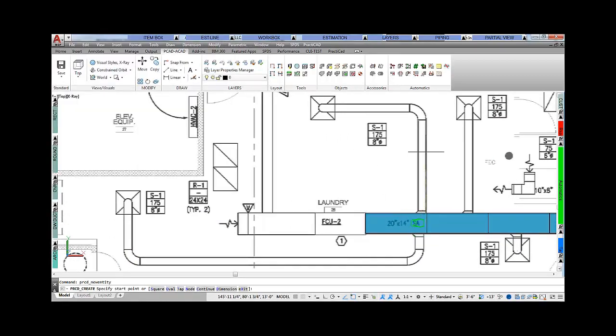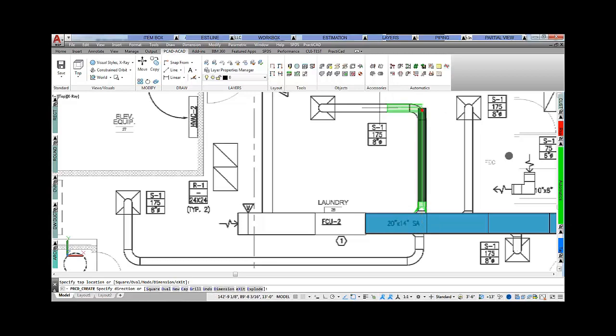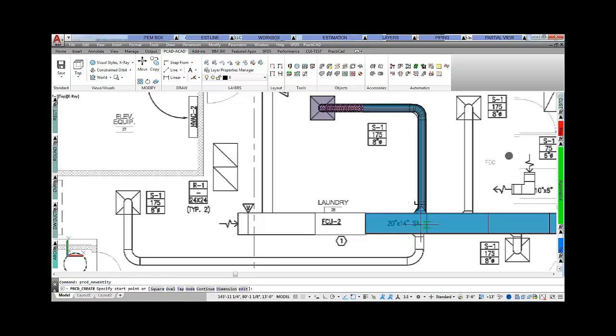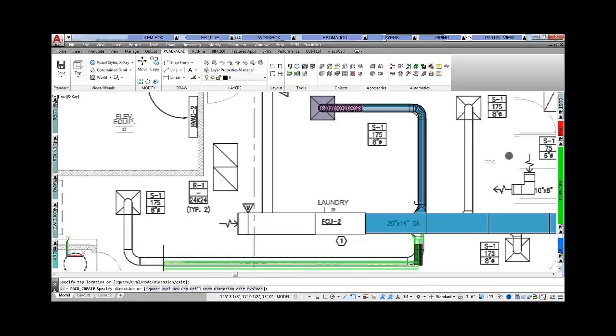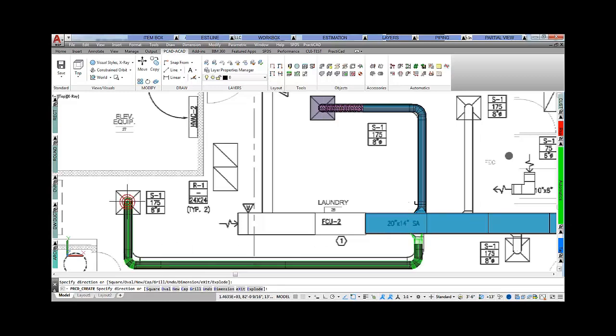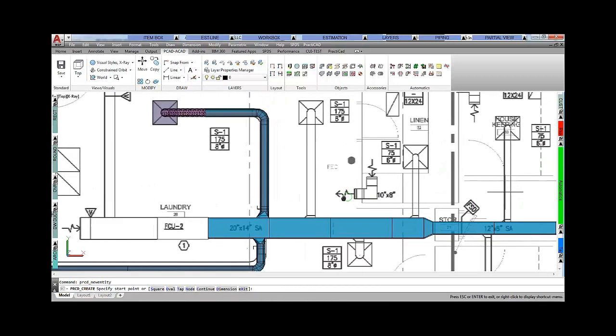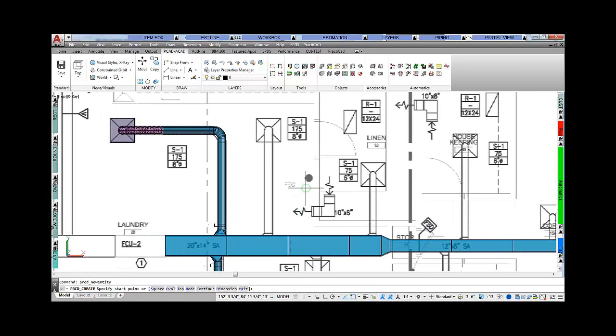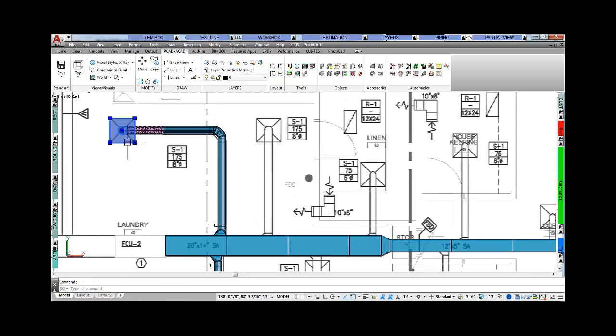Watch as we click on the main run and PractiCAD generates an STOD fitting as a tap, then runs straight pipe for our next click, automatically generates a purchased elbow on the turn, and inserts the GRD wherever we want. This includes the proper relative elevation and proper min-max flex length.